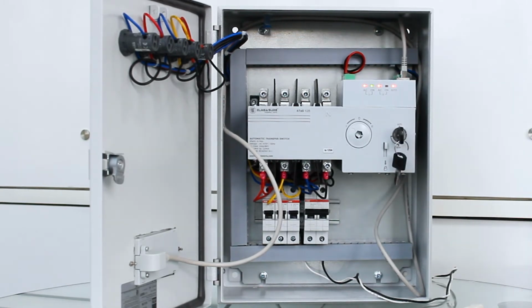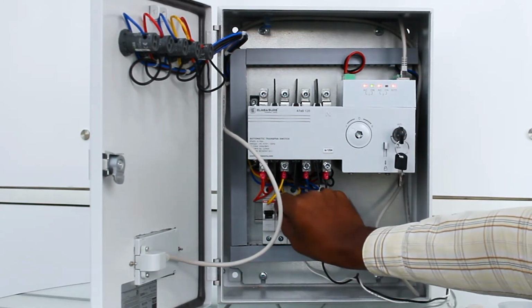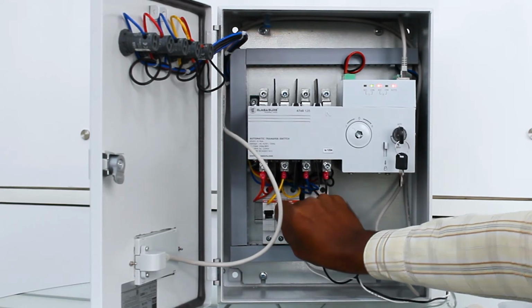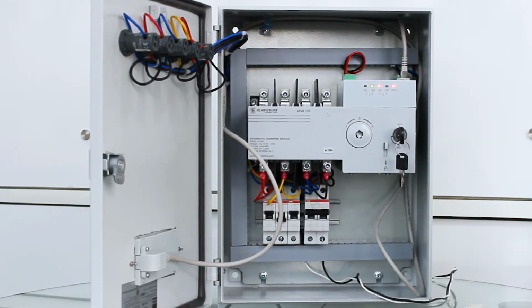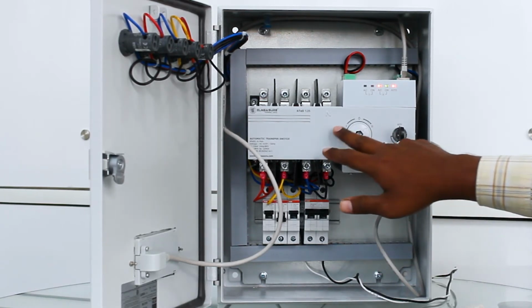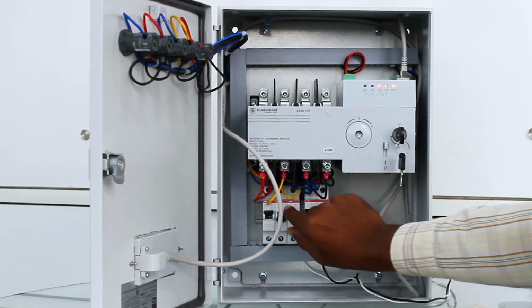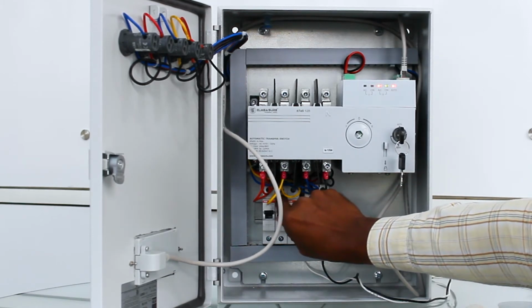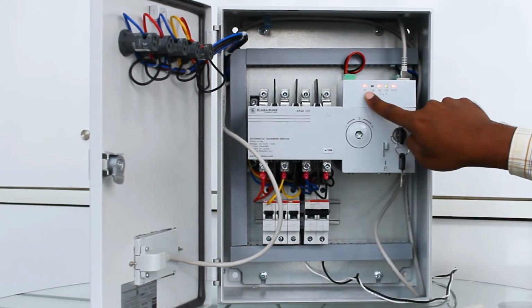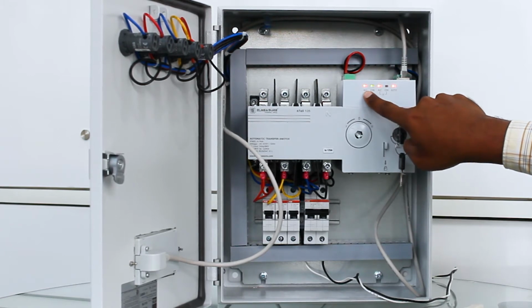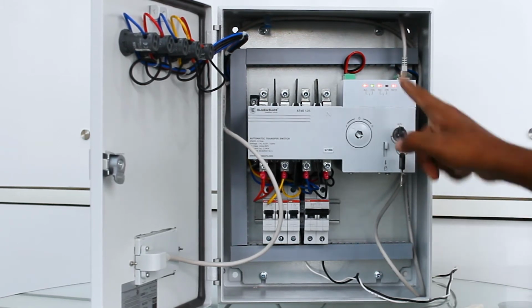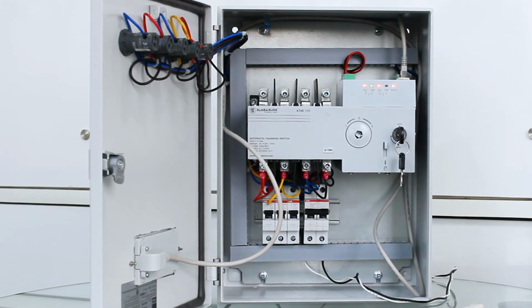Now I will put the ATS in auto mode. With the ATS in auto mode, if I switch off any one of the phases on the transformer side, you can see the ATS first initiates to start the generator, and immediately it moves from transformer to generator. Again I restore the transformer supply. Now you will see the transformer healthy and load on indication. Automatically it will move from generator to transformer.